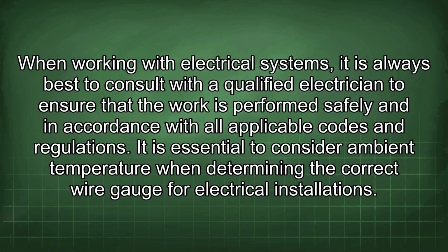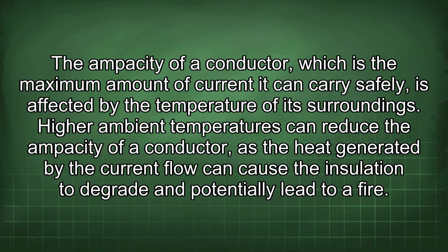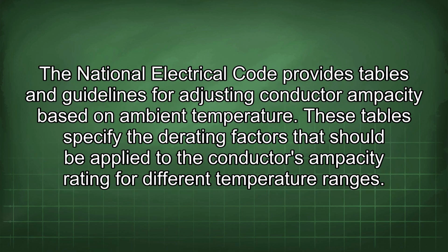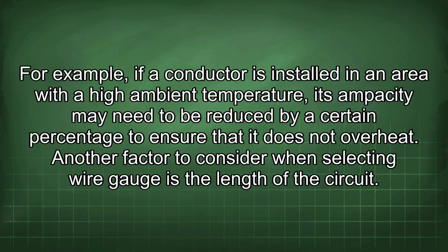It is essential to consider ambient temperature when determining the correct wire gauge for electrical installations. The ampacity of a conductor, which is the maximum amount of current it can carry safely, is affected by the temperature of its surroundings. High ambient temperatures can reduce the ampacity of a conductor, as the heat generated by the current flow can cause the insulation to degrade and potentially lead to a fire. The National Electrical Code provides tables and guidelines for adjusting conductor ampacity based on ambient temperature. These tables specify the derating factors that should be applied to the conductor's ampacity rating for different temperature ranges. For example, if a conductor is installed in an area with a high ambient temperature, its ampacity may need to be reduced by a certain percentage to ensure that it does not overheat.